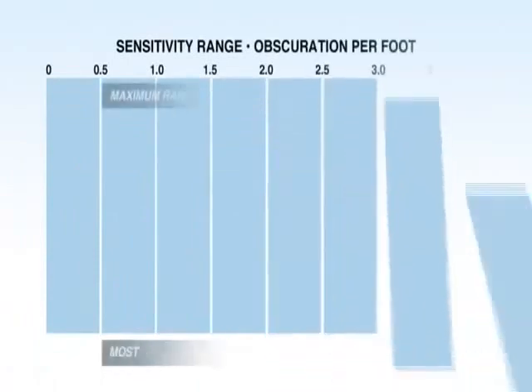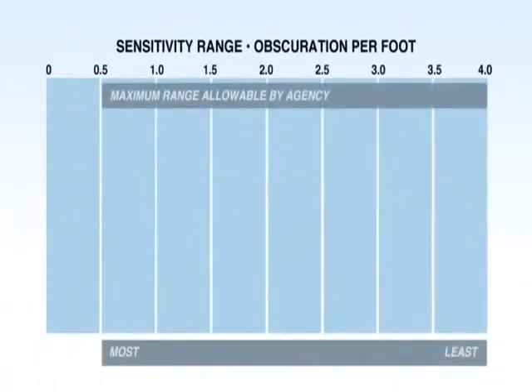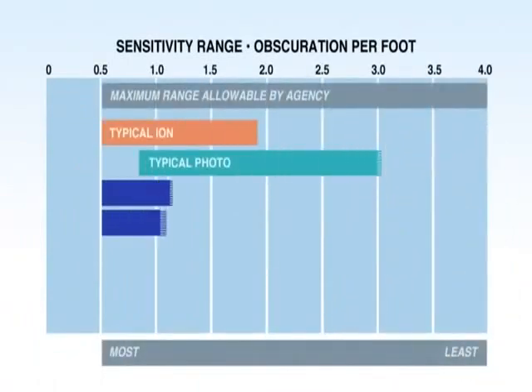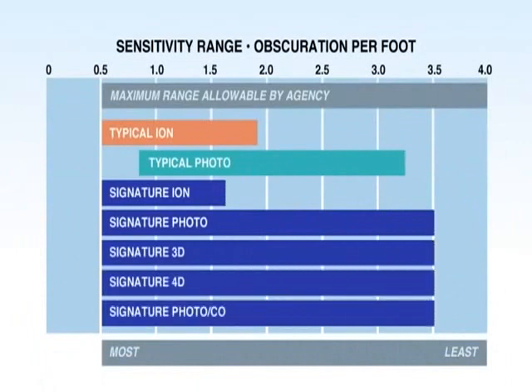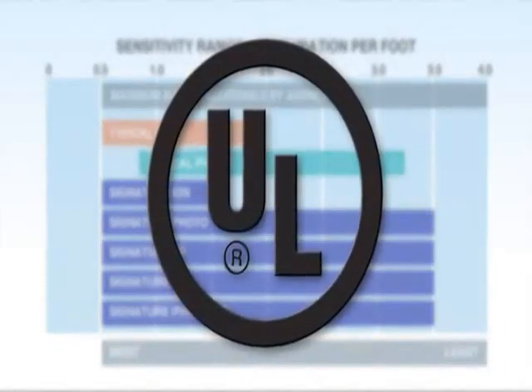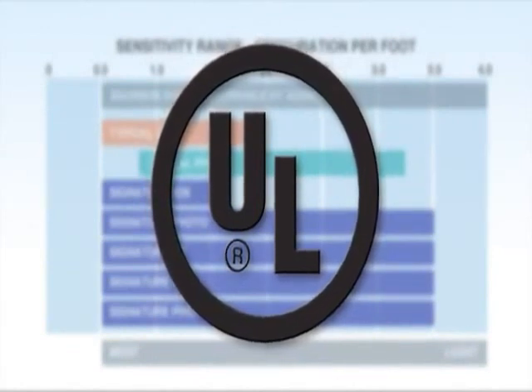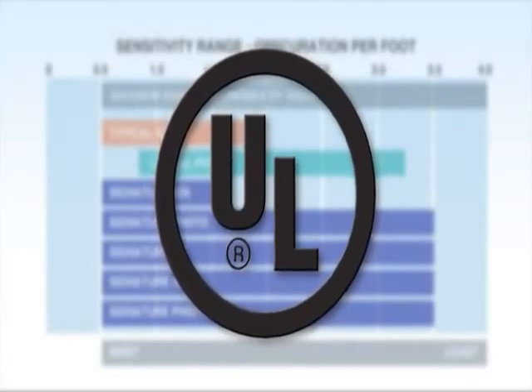Thanks to Signature Series design stability and unique characteristics, the sensitivity range of our detectors surpasses industry standards. In fact, Signature Series and the related control hardware has been authorized by Underwriters Laboratories as an approved sensitivity test meter. This means the system does not require a separate calibration sensitivity test in order to comply with NFPA 72.